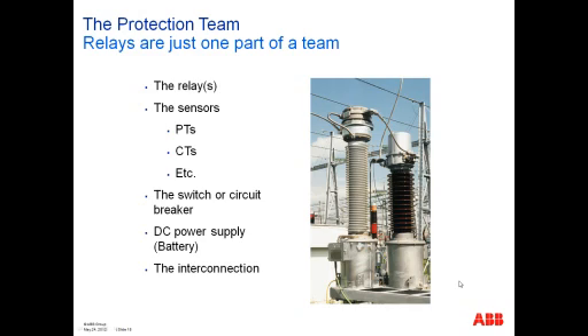Of course, you also have the switch or circuit breaker that you are trying to control. You're going to make some measurements and then operate the switch or circuit breaker to provide some type of corrective action. And you have the DC power supply, which must be maintained such that the relay stays in operation, and of course the interconnection of all these devices.